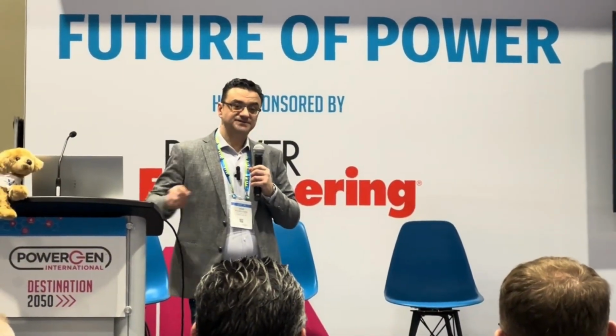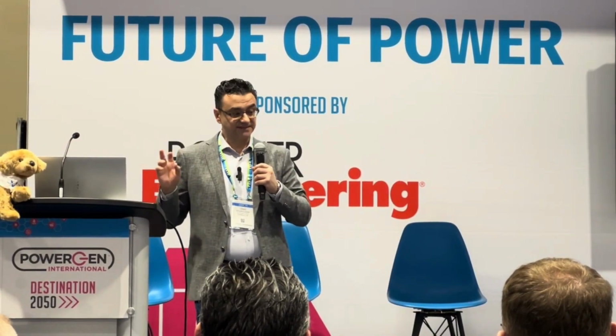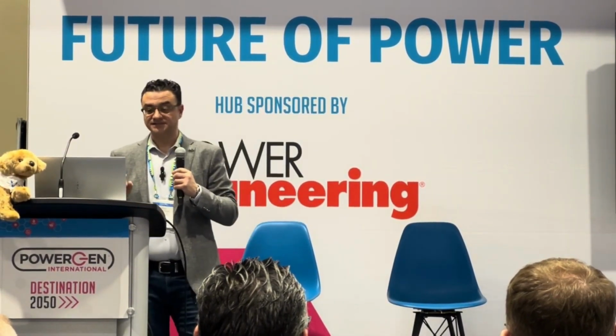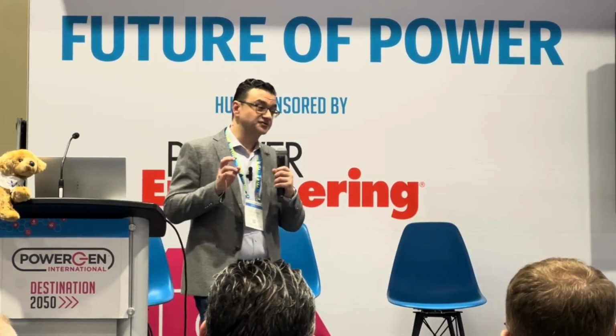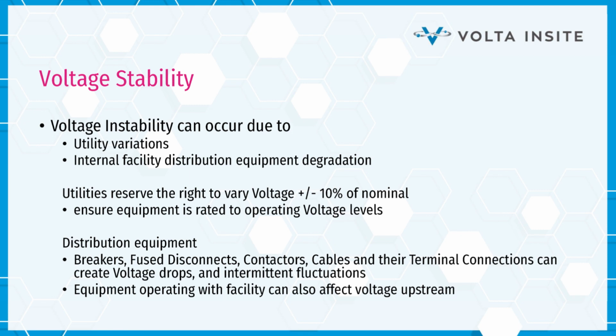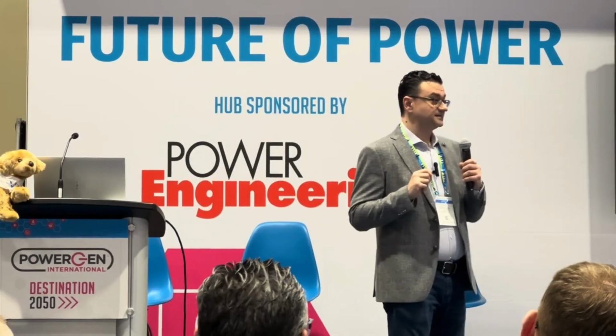So why do we have things like voltage instability, and how does it come about? There's usually two culprits. There's utility variation, so something's happening on the utility side, or there's internal facility distribution equipment that has undergone some type of degradation. On the utility side, it's important to remember that utilities have the ability to vary the voltage plus or minus 10%. And that means that if you're specifying equipment within that facility, you should be able to handle some of those transients. And we'll get to that.